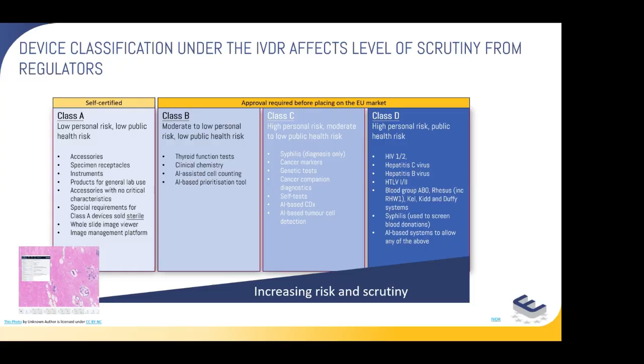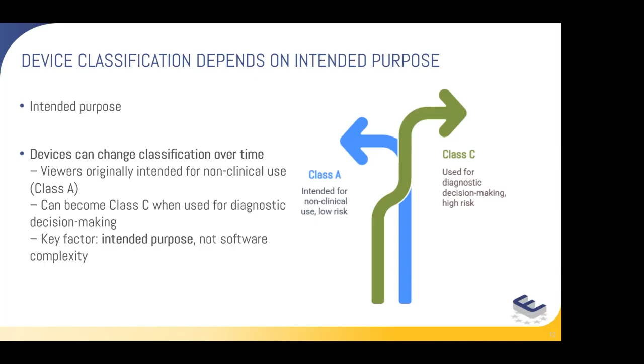Classification isn't always straightforward, though, and usually involves judgment calls that depend on the specific intended purpose, the claims that you want to make with the device, and the clinical context of use. So as I said on my previous slide, the same viewer can be both a Class A and a Class C device, depending on what you want to do with it. And so under the IVDR, device classification is driven by the intended purpose. And the key thing here is the role the device plays within that clinical decision-making process. As the intended purpose changes, you need to continually reevaluate to make sure that the classification of the device is still matching the intended purpose of the device. So the complexity of the software essentially has nothing to do with device classification under the IVDR. It is still, even for digital pathology devices, driven by the intended purpose of the device.